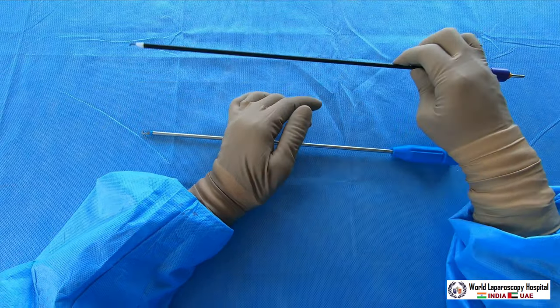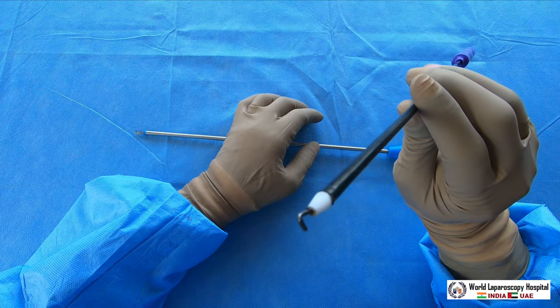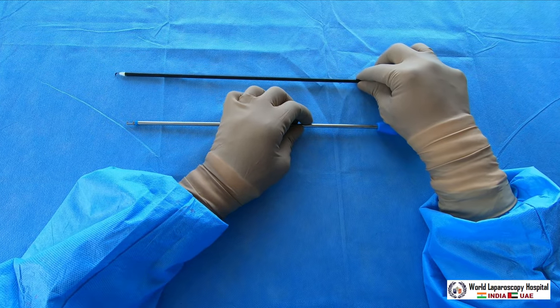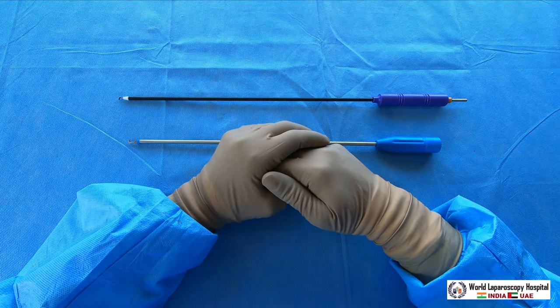As we know, the frequency of electrosurgery is from 500 kilohertz to 3.3 megahertz, so the higher end of the frequency is required for the bipolar hook. But with the monopolar hook, you don't have to worry about the electrosurgical generator — even a simple electrosurgical generator can work with the monopolar hook. So these were the different types of hooks discussed today. Thank you very much for watching this video, have a nice day.